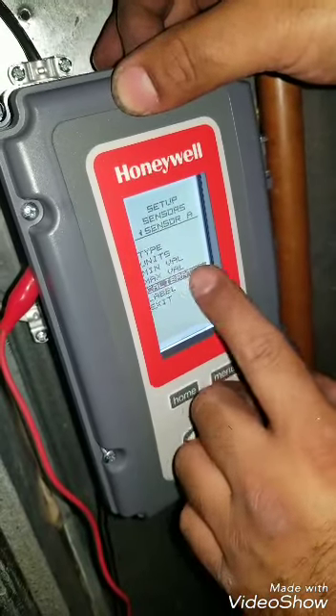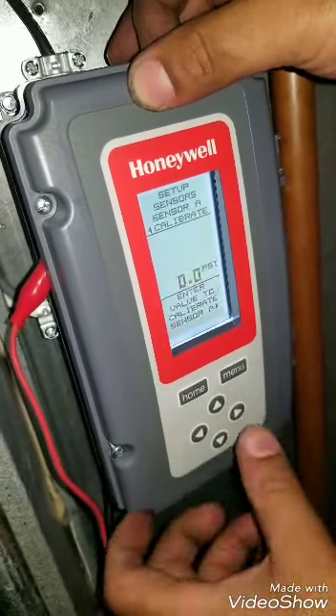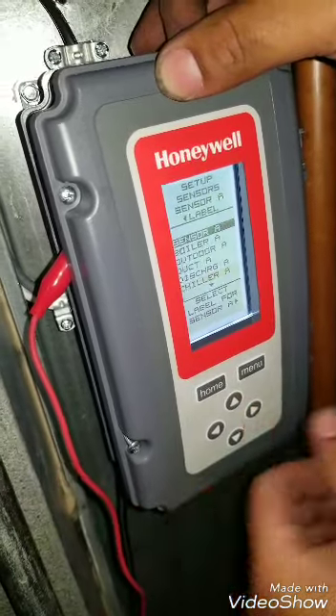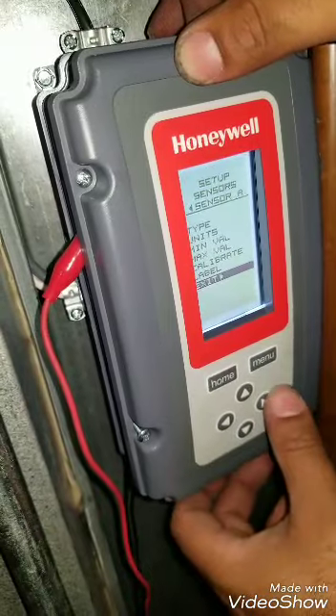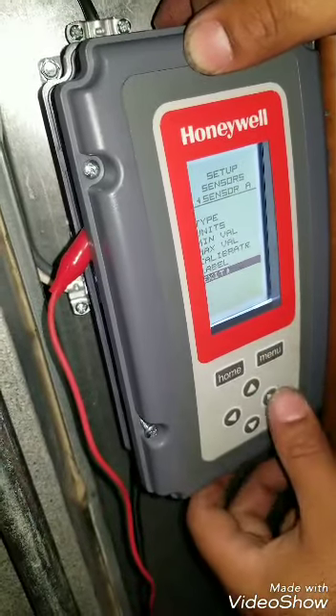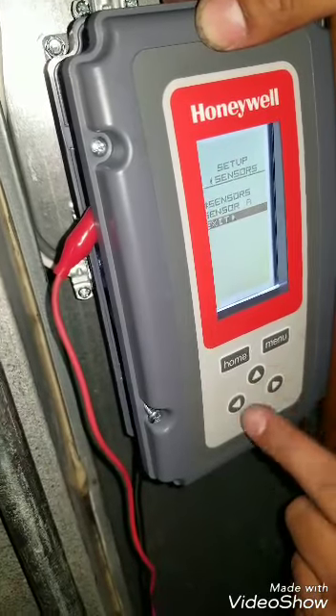Alright, so 0 to 500. Min 0, max 500. Calibrate, you could leave that 0. Label, you could call it whatever you want. We can call this discharge, because it's discharge pressure, right? Okay. And then exit. That's it. Exit is basically the enter button. This is back, up, and down, obviously. Or you could just hit home and go all the way back.